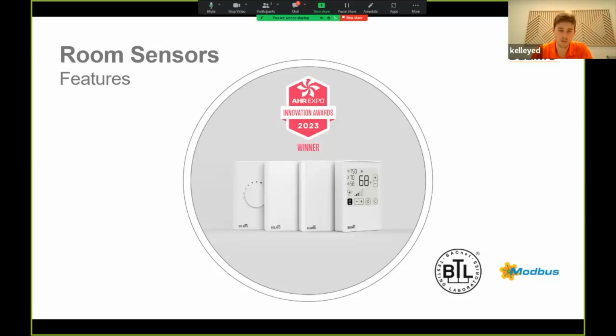So Belimo offers room sensors for air quality monitoring. Just as a side note, room sensors are different from thermostats because they don't control things directly. They measure the air quality. They'll send that information back to a controller or a BMS, and then that controller will do something. For example, turn on the heating, air conditioning, a fan, et cetera. Belimo offers passive room sensors. The passive ones measure temperature. We have different outputs: PT100, PT1000, Nickel 1000, NTC10K2, 10K3, and 20K. They have a manual override button to wake up the system, and they've got an optional set point dial.